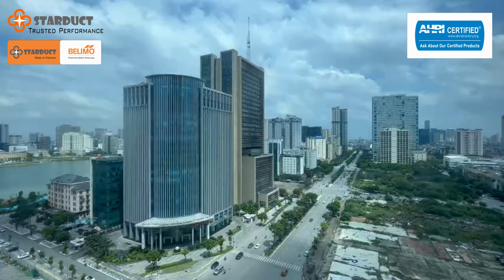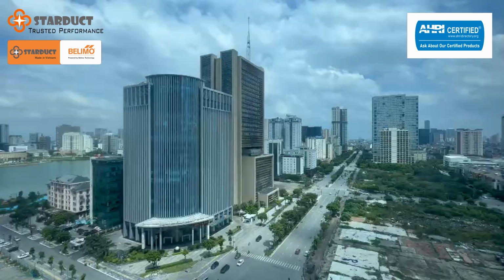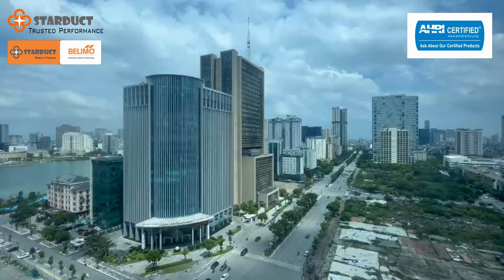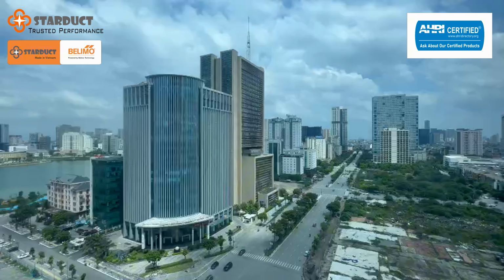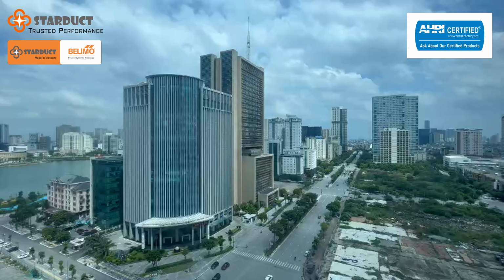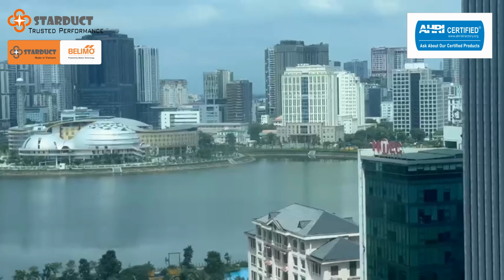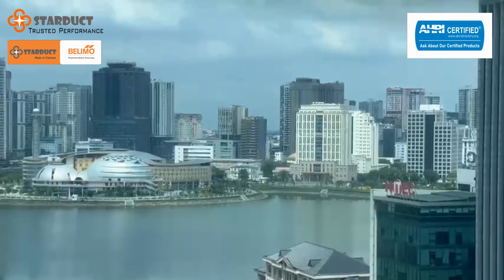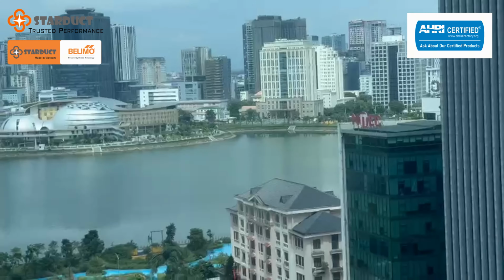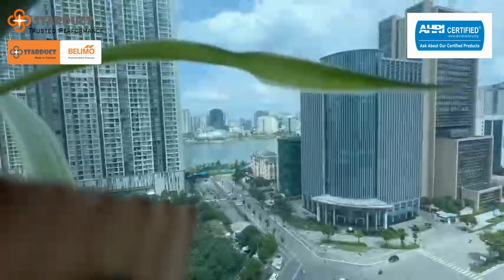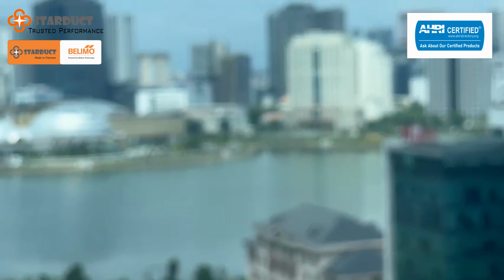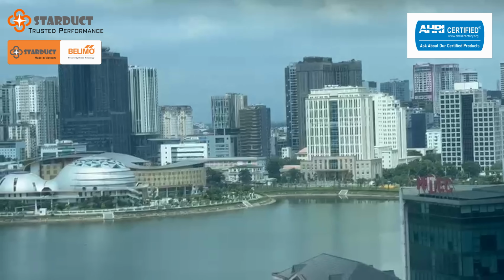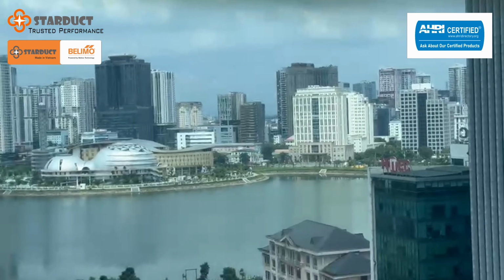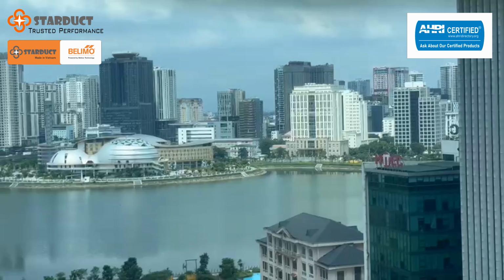You get the simple things like the little sensing tubes getting clogged with dust over time. Or maybe they get kinked during installation or maintenance. Or, and this is a big one, the high and low pressure tubes get connected backwards. That gives you this infamous negative delta P reading, which mathematically makes the flow calculation impossible. It's nonsensical. So my argument here is that relying purely on the initial setup and maybe some digital checks isn't enough. You need that focused, physical scrutiny. The emphasis has to be on the health of that delta P sensor itself.